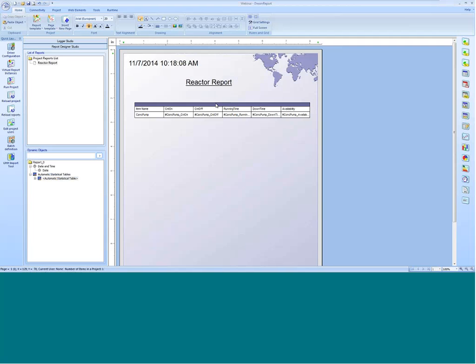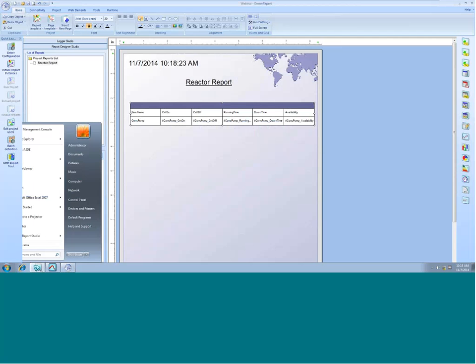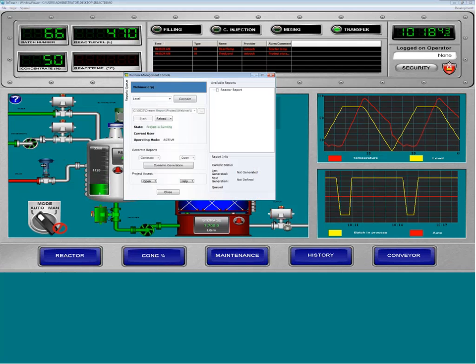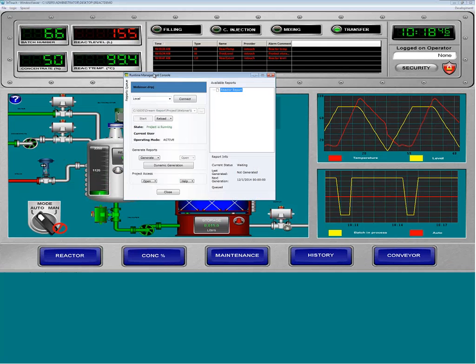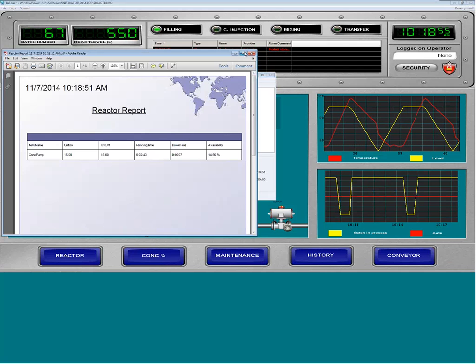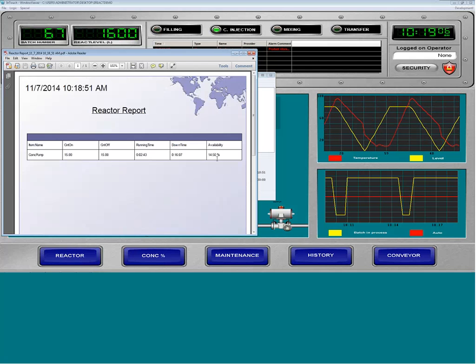I'm going to make this object a little bit bigger, load the project, and save the changes. I'll stop the other running project and test that we have good data for uptime/downtime of our pump. I'm using the Wonderware Historian as a data source and have InTouch running in the background. Imagine a pump or motor running in your plant — here's my concentrate pump, and right now it's not running. I'll highlight my report name and click Generate. The report automatically opened up as requested. I can see how many times this pump turned on and off, the total running time, total downtime — I've had 14.5% availability, meaning it's been running 14% of the time over the last hour.